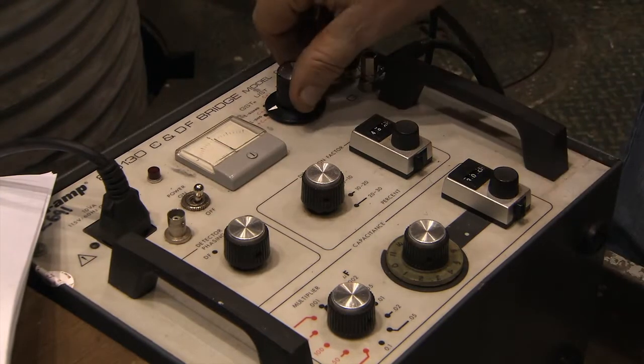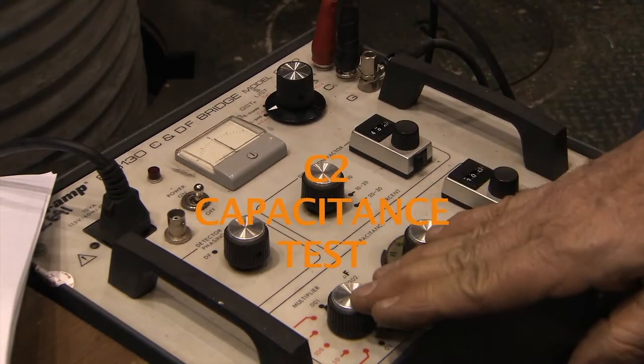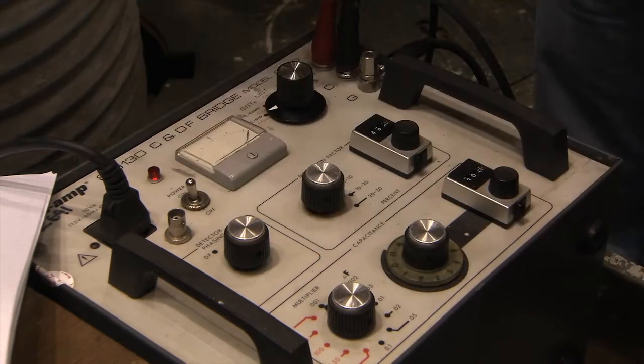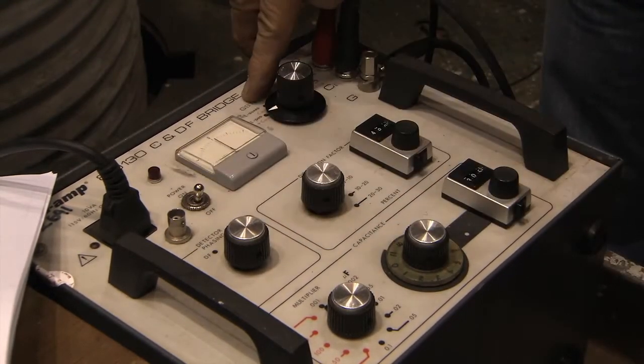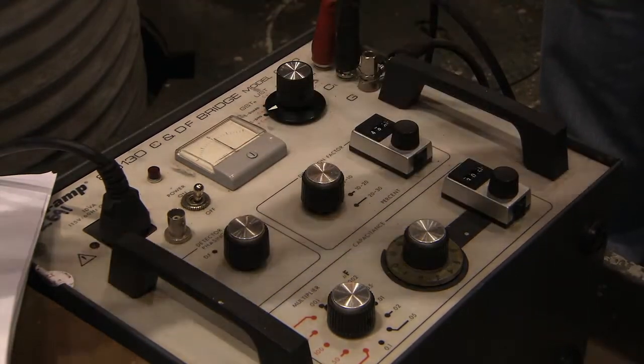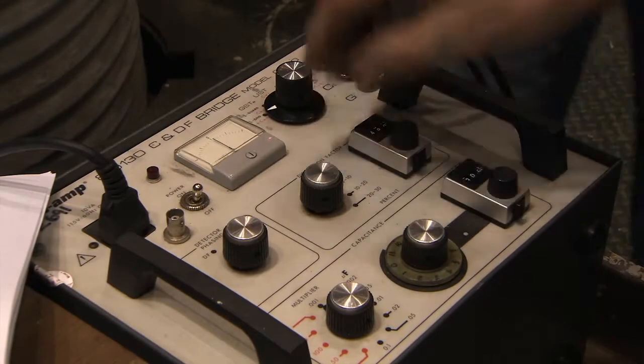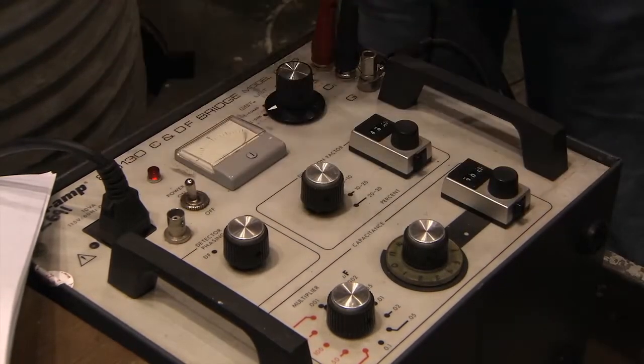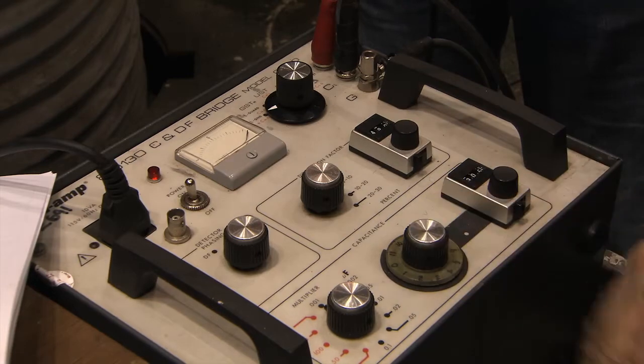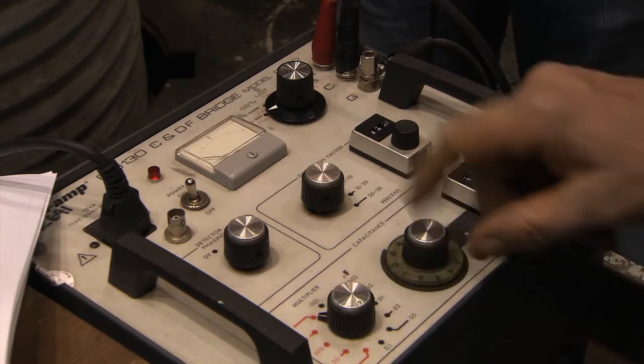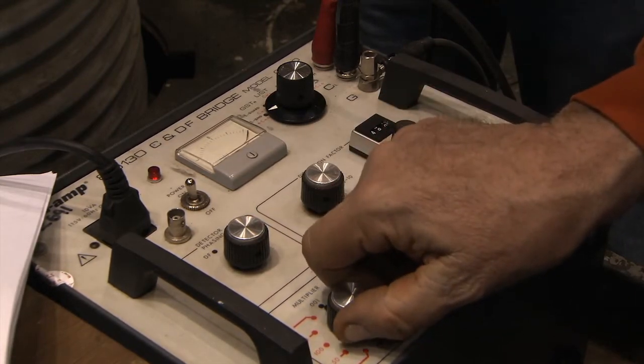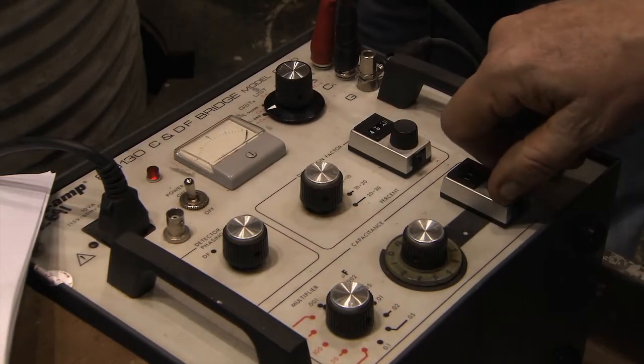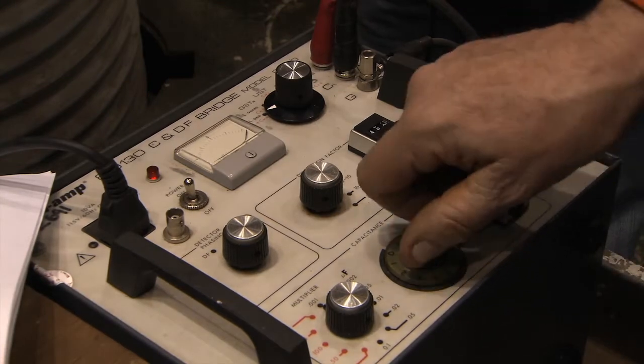Okay. So we're going to do a capacitance test first. This is a grounded specimen test, and the low is now grounded to the flange. So that's why it's in this position. Now we turn on the power. We're going to do a capacitance test first. We're at 500 here. It's too high. So that's where we have to be there. Yeah, and then back. Oh, is it not on? No, it's on. Okay. There you go.